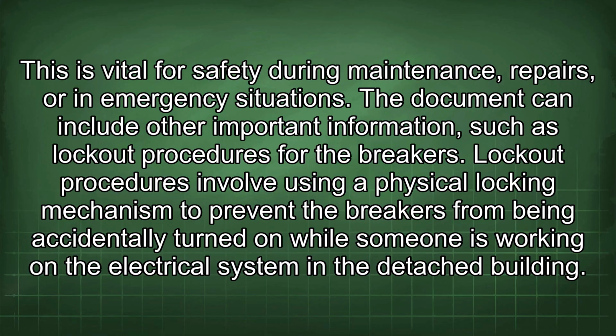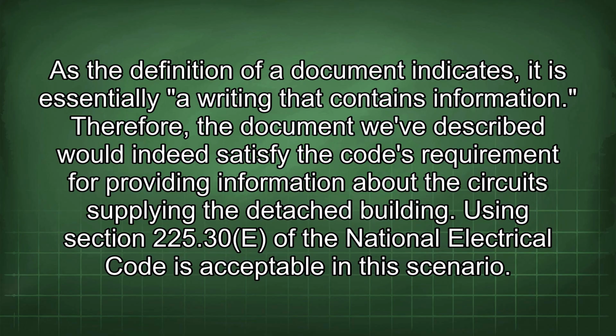The document can include other important information, such as lockout procedures for the breakers. Lockout procedures involve using a physical locking mechanism to prevent the breakers from being accidentally turned on while someone is working on the electrical system in the detached building. As the definition of a document indicates, it is essentially a writing that contains information. Therefore, the document we've described would indeed satisfy the code's requirement for providing information about the circuits supplying the detached building.